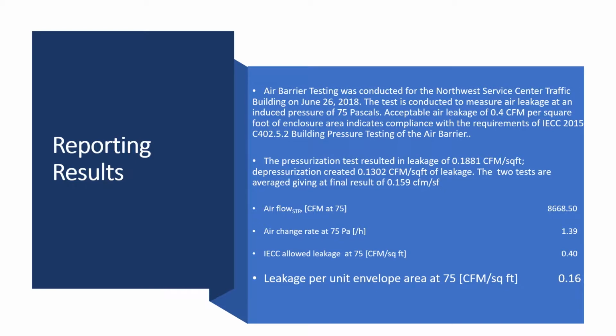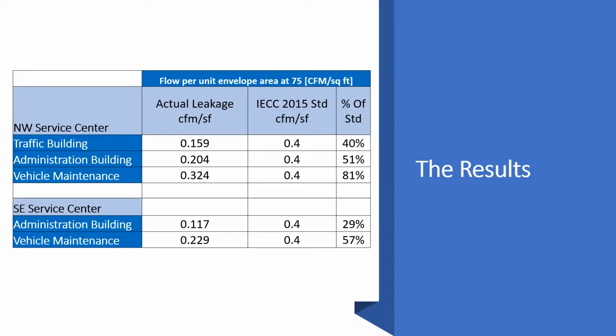That was one of our better performers. Put the table up here so you can see just where we came out. So the traffic building was probably one of our better performances at the Northwest Service Center. We were 0.159 or 0.16 CFM per square foot versus the standard of 0.4. So we achieved 40% of the standard.